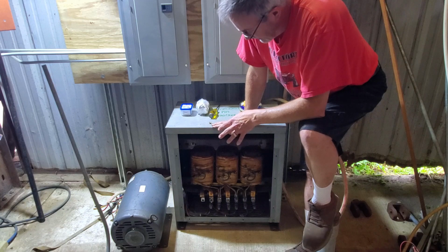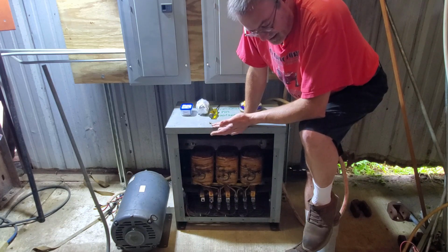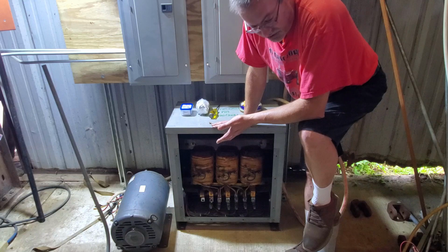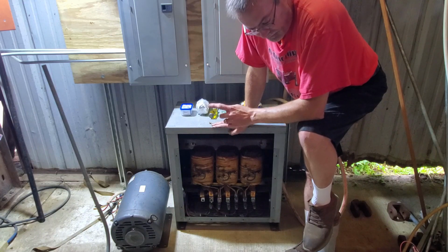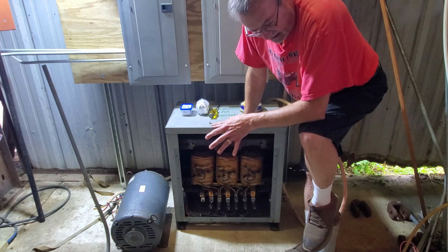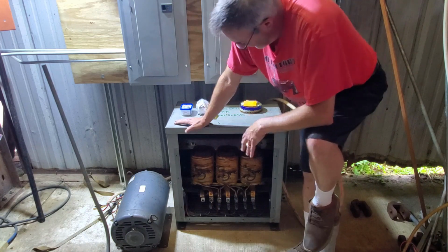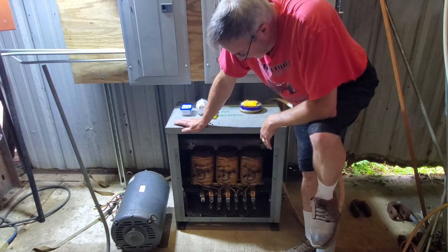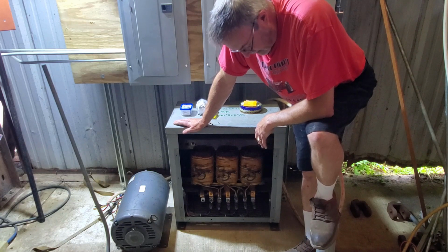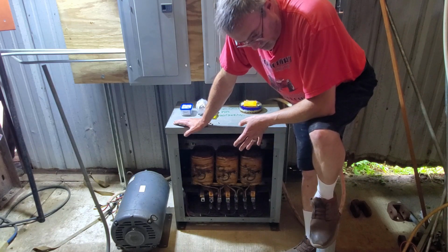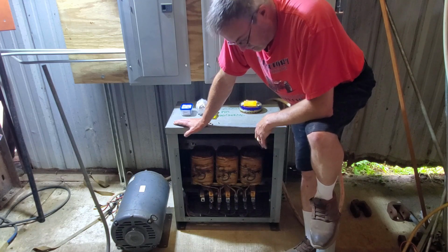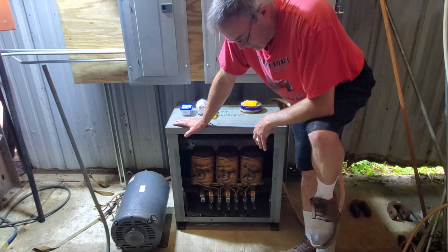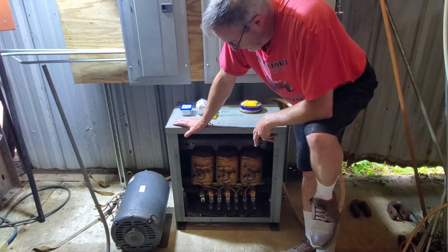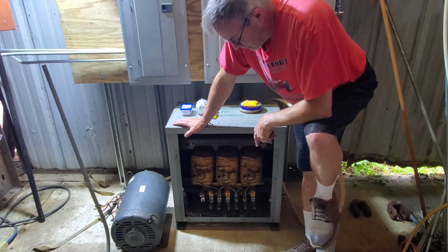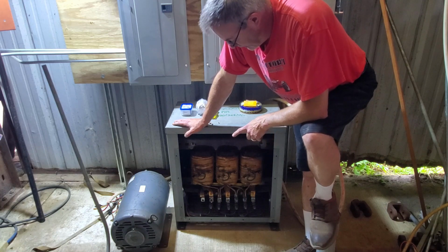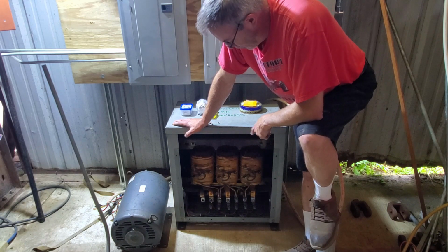The nice thing about running that motor on high voltage is it's like 27 amps, so I could use 10 gauge wire on the motor. Everything gets cut in half on the current readings you see, and that's one of the nice advantages of 460 volts, you can down gauge all the copper going to your equipment, which is much cheaper. At some point, especially with the price of copper today, it won't take much for the additional cost of heavy gauge copper to be more expensive than one of these transformers.